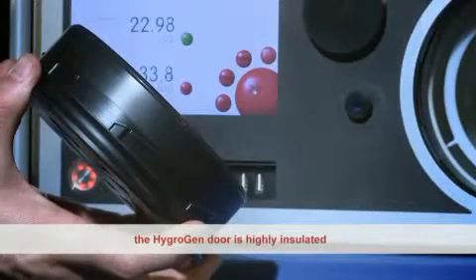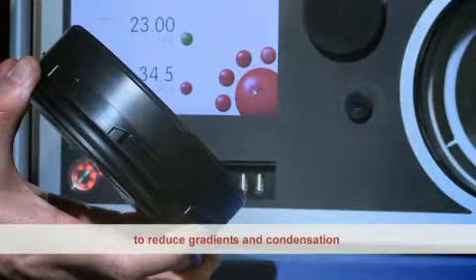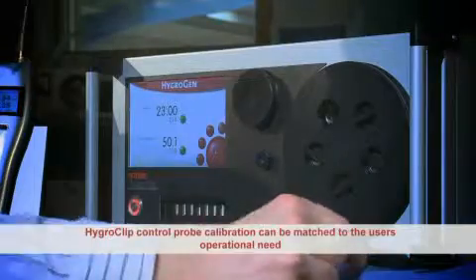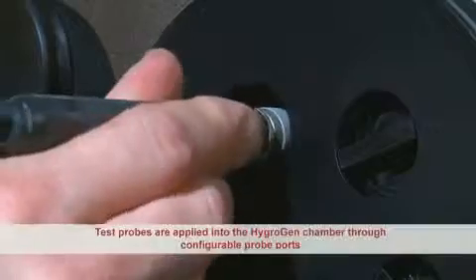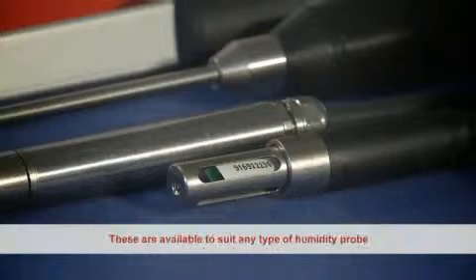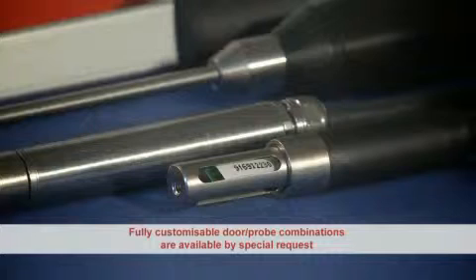The HygroClip probe is carefully positioned to provide the best possible chamber control. To achieve temperature stability and gradient specifications, the HygroGen door is highly insulated and includes peripheral temperature control to reduce temperature gradients and condensation when running at high temperature conditions. The HygroClip control probe can be calibrated exactly to match the user's operational need. Test probes are applied into the HygroGen chamber through configurable probe ports, available to suit any type of humidity probe. Fully customizable door probe combinations are available on special request.